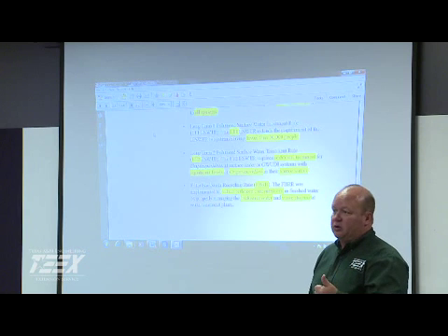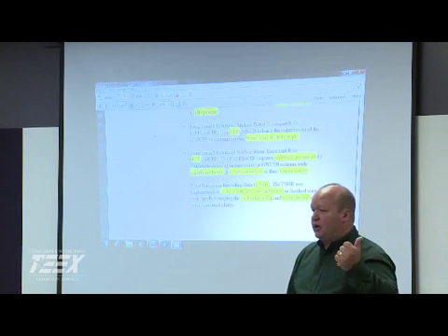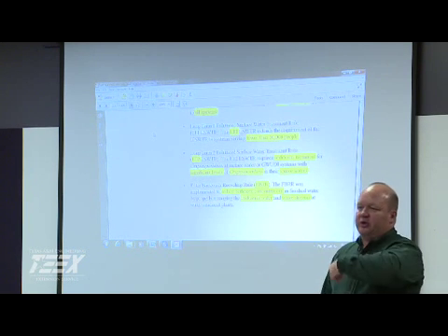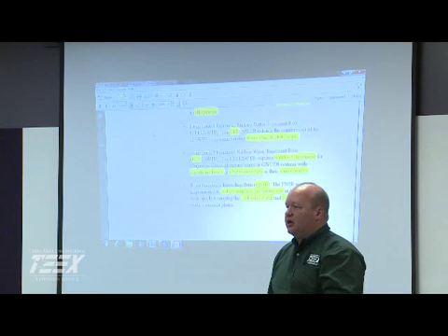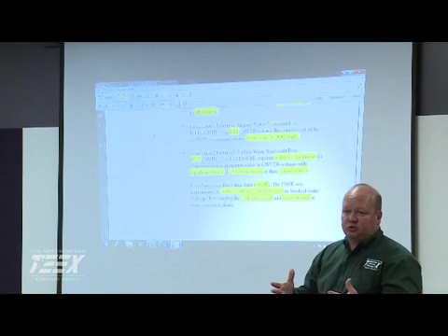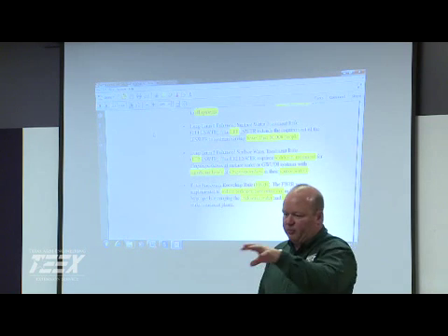And filter backwash recycling rule, big deal. Where's that water coming from? Where are you sending it to? And if you're recycling it, you're concentrating those contaminants and you're putting it back up into your source water. So now you have a greater potential of actually contaminating your water, because if you have a filter breakthrough, now you've got a high concentration. So several different sources of your plant were not supposed to be recycled.